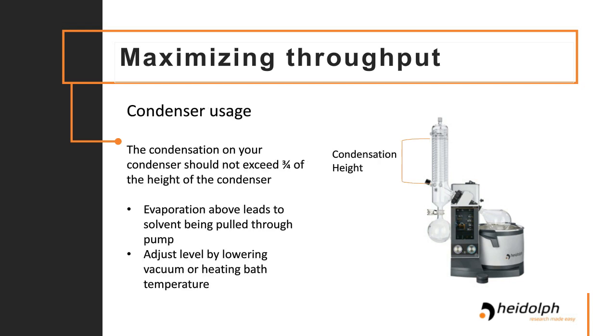So a key strategy in maximizing your throughput is to make sure you're not losing any of the solvent that you're evaporating off. One of the big ways to do this is to not exceed the 3/4 height of your condenser with the liquid that you're evaporating. If you evaporate too strongly, you'll find that some of your solvents that you've evaporated off can get pulled through your vacuum pump, which not only leads to you losing that solvent, but can potentially harm you as it's getting pulled into the environment. The easiest way to stop that from happening is just to monitor it.